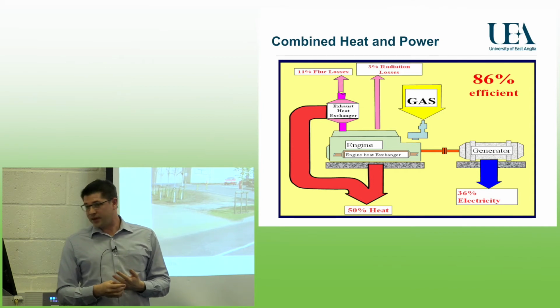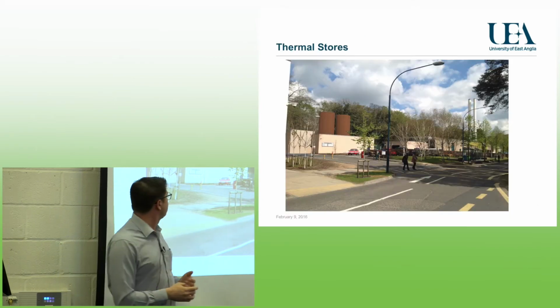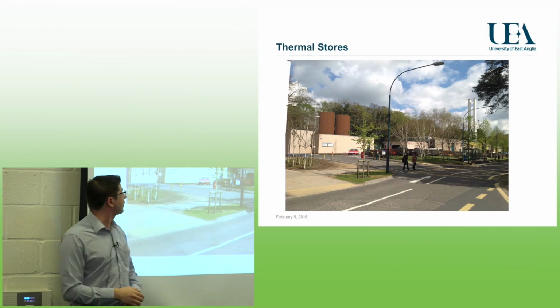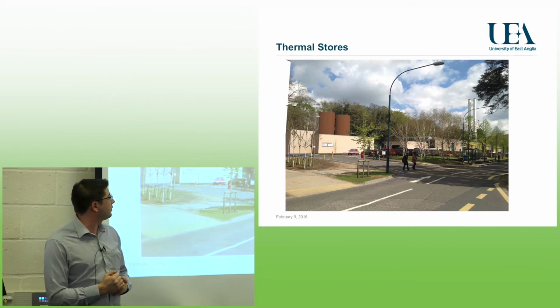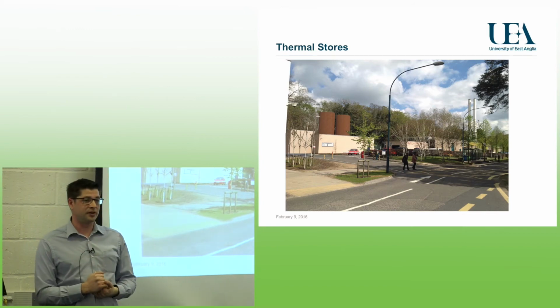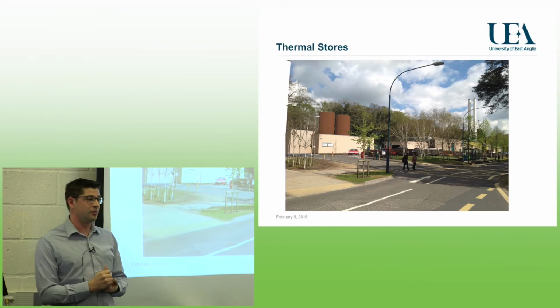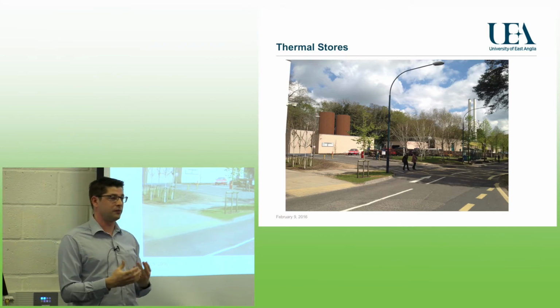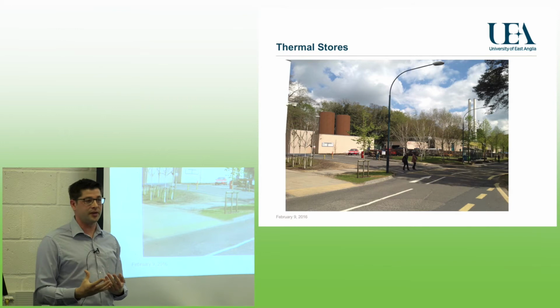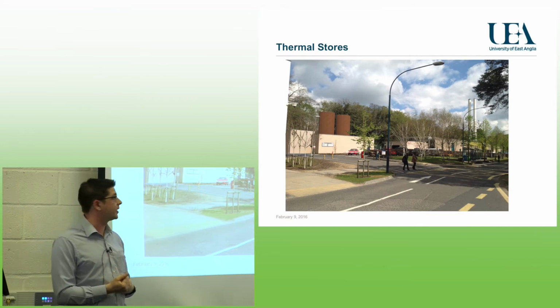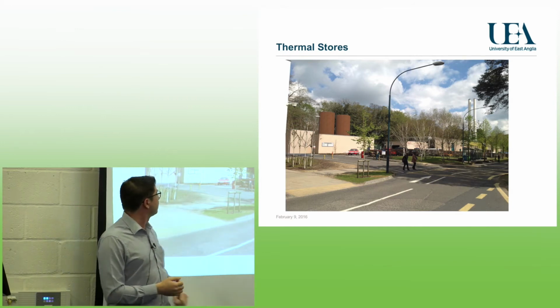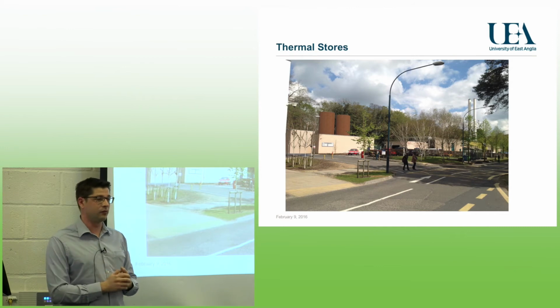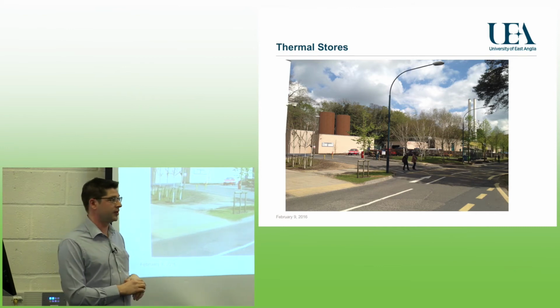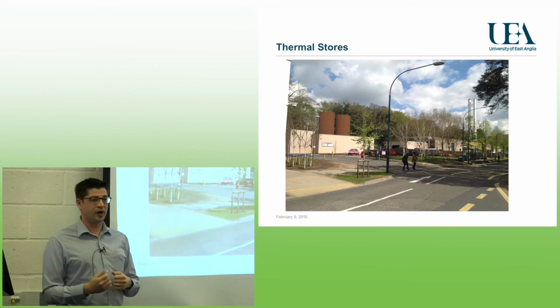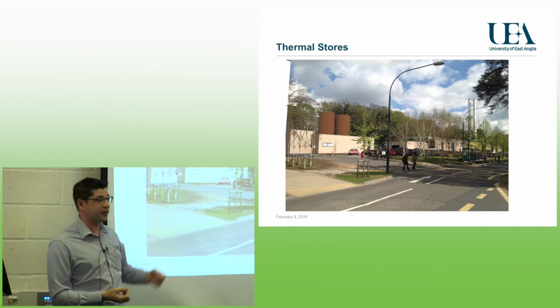One thing you'll see being delivered next weekend is 2 thermal stores, which you might just be able to see in the background here. We're putting these in to maximise the efficiency of our engines. At the moment, overnight potentially, we can't use all the heat coming off the engines, so we have to reject some of it to atmosphere. So we're going to be putting in 220,000 litres of water, which will heat up to 90 degrees overnight. Then instead of having to fire boilers the following morning, we can just bring the heat out of those.